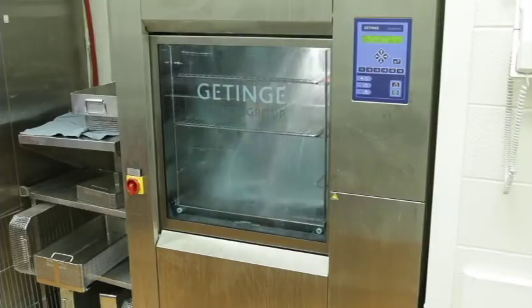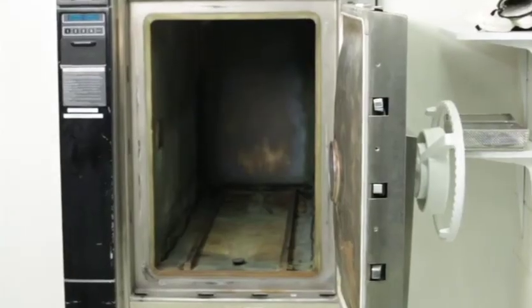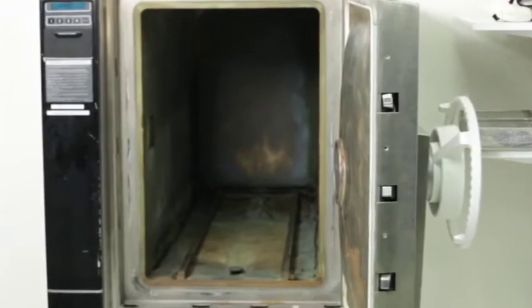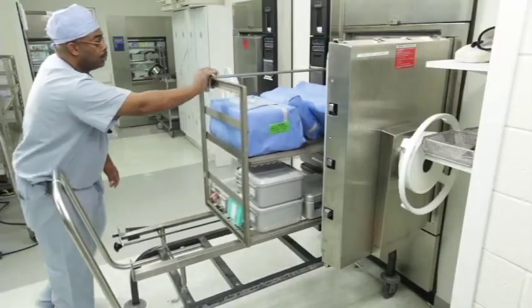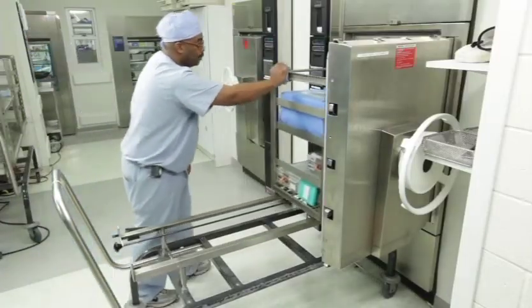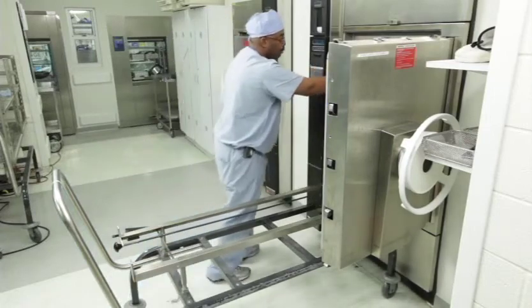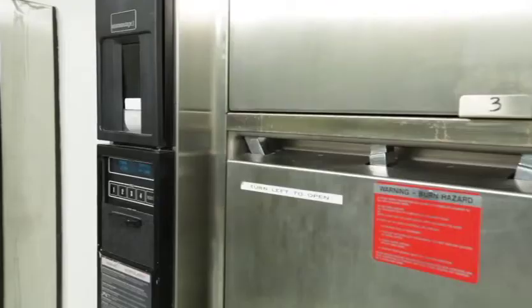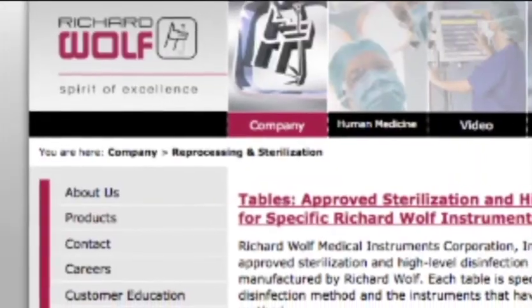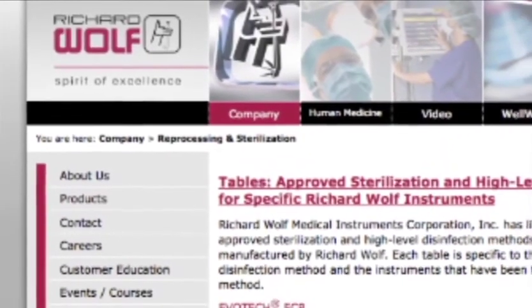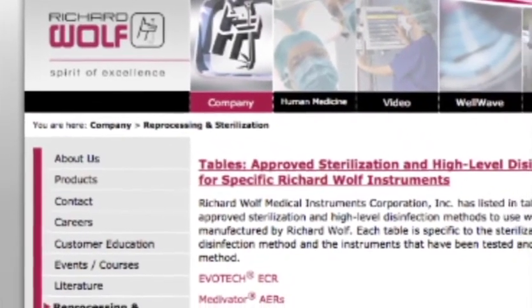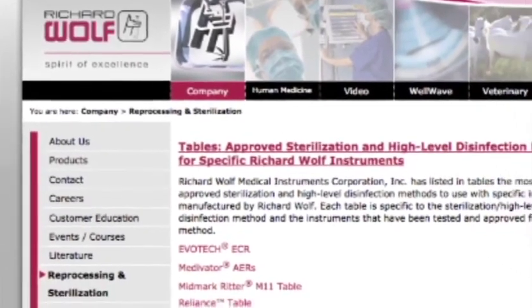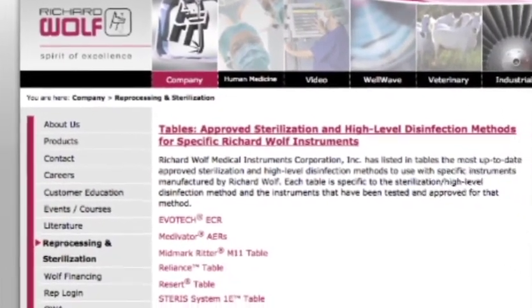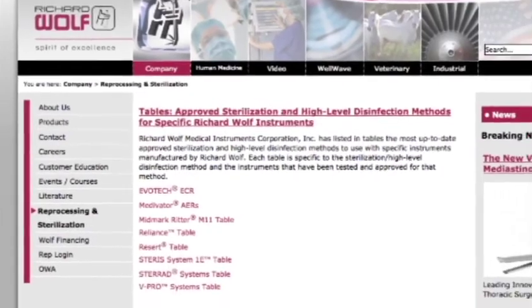Most Richard Wolf rigid endoscopes are heat stable and have been validated to autoclave in a pre-vac steam sterilizer at 270 degrees for 4 minutes with a 20 to 30 minute dry cycle. Some rigid endoscopes may also be processed in low-temperature sterilizers. Please visit us at www.richardwolfusa.com for the most up-to-date information regarding alternate reprocessing methods, including instruments validated for low-temperature sterilization.